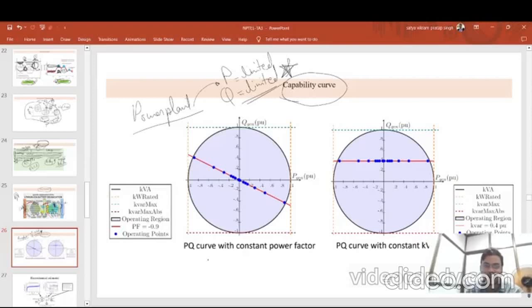The capability curve gives two curves: a PQ curve at constant power factor as the first curve, and a second curve with constant reactive power support.